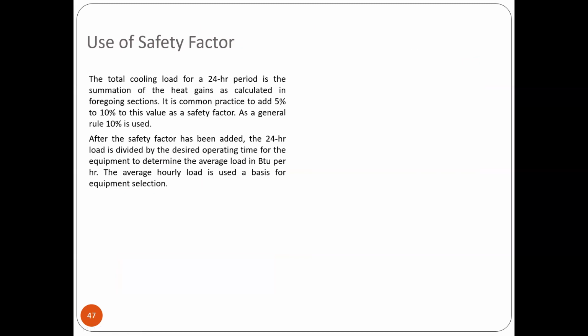Use of safety factor. The total cooling load for a 24-hour period is the summation of the heat gain as calculated in the foregoing section. It is common practice to add 5% to 10% to this value as a safety factor. As a general rule, 10% is used. After the safety factor has been added, the 24-hour load is divided by the desired operating time for the equipment to determine the average load in BTU per hour.